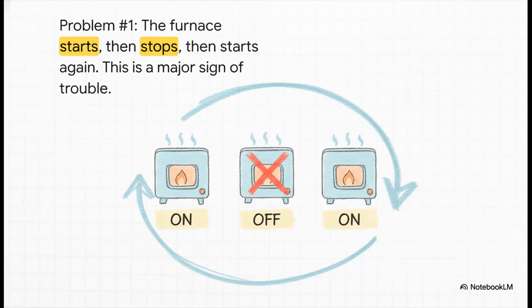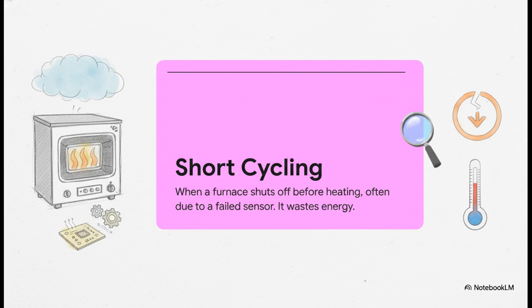All right, first up is this absolutely maddening scenario. You hear the furnace kick on, you feel a little bit of heat come out of the vents, and then nothing. A few minutes go by, and it tries all over again. This isn't just annoying, it's a huge red flag. This is what's known as short cycling. The furnace is actually shutting itself off as a safety measure before it can really do its job. The cause could be something like a dirty flame sensor or a faulty safety switch, but whatever it is, this is incredibly inefficient.